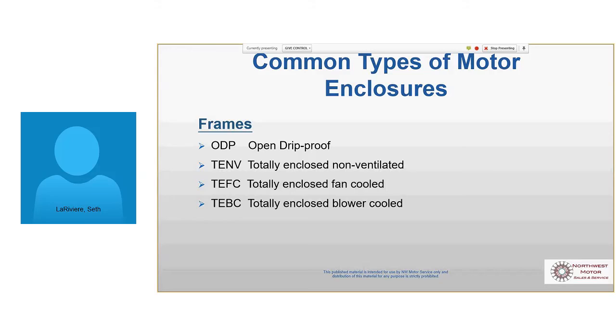Anything other than that, you really need to be looking at totally enclosed, either a totally enclosed non-vent. You don't see a whole lot of those. Those are usually time-rated motors, like 60-minute duty. You see them on cranes is a good example, that you can only run your crane for so long before it gets too hot. But they're not usually run all the time. If you have a crane in your shop, you use it to move something and it cools off for 15, 20 minutes and you can use it again. So they're duty cycle rated.